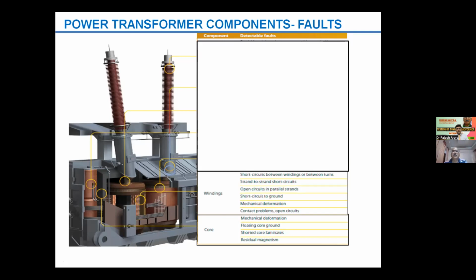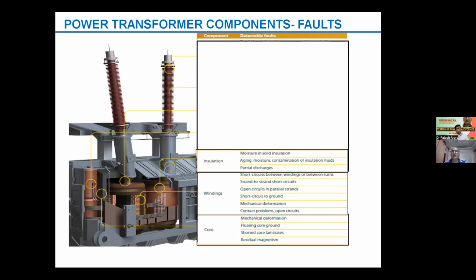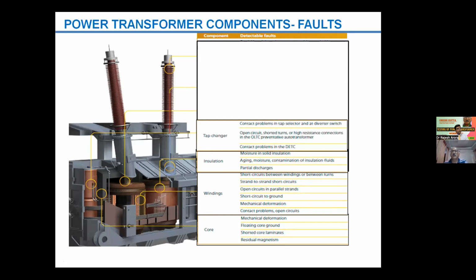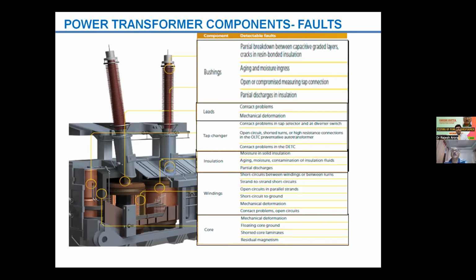Winding related issues are listed like that: short circuit between winding turns, strand to strand short circuits may be there, then open circuit in parallel strands, short circuit to ground like that. And in insulation, moisture may be there, aging related issues may be there, contamination may take place, PD may take place with the insulation, then issues with the tap changers may be there, different kinds of issues. Then lead connections, contact problems, mechanical deformation with the connections, etc.